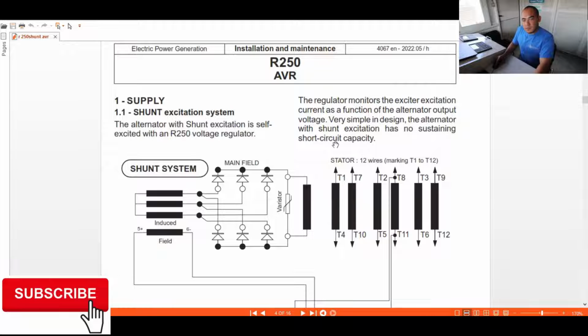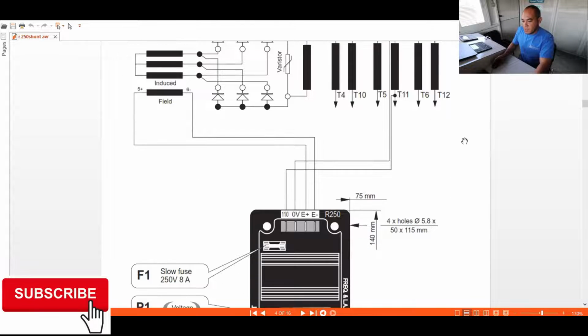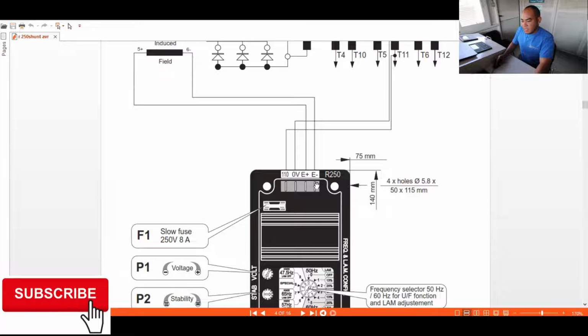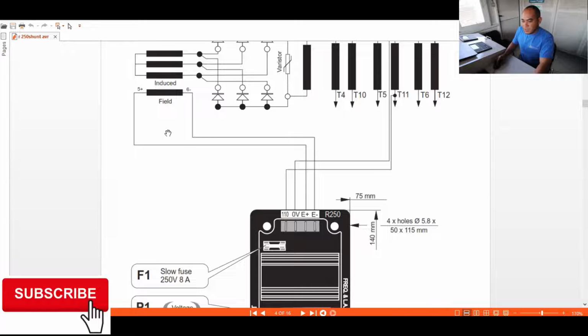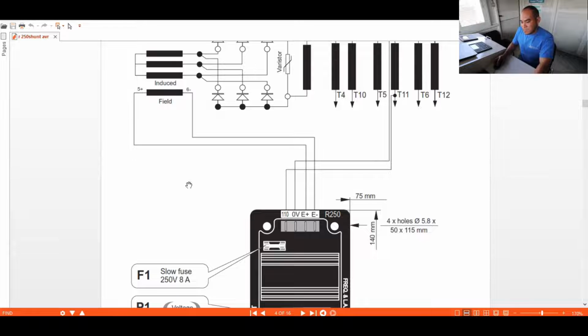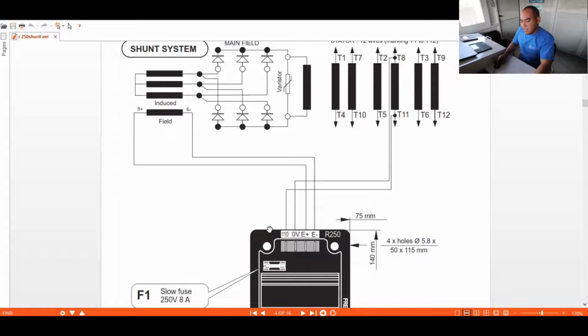There's no short circuit capacity. So here are our connections. This is your E plus and E negative, which, as I told you, is your exciter field. So it is connected as positive and negative. Here is where you can also inject the battery for your excitation process. You just remove the connection here and take this wire for your excitation if you have some trouble. Your sensing is all around 110 volts only. We will talk about that further down.